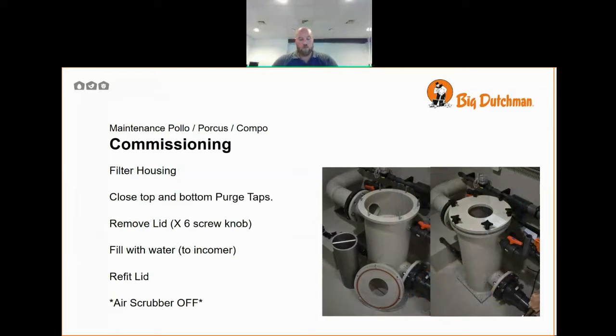The filter housing. The filter housing comes with a top and a bottom tap. These are to allow water to run back from the filter to the process pit to empty, and a further one at the top to allow air to enter and purge water from the filter housing. Remove the lid by the 6 screw knobs. Fill with water up to the incoming pipe. As you can see in the top of the open filter housing on the picture, that's the opening that you can see. So fill up to that level. Refit the lid in reverse of removing it.